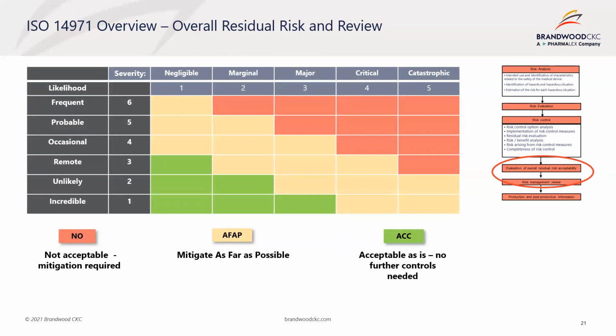ISO 14971 allows the manufacturer to perform a benefit risk analysis for those risks that are not judged acceptable using the criteria established in the risk management plan and for which further risk control is not practicable. The benefit risk analysis is used to determine if the residual risk is outweighed by the expected benefits of the intended use of the medical device. Benefit risk analysis cannot be used to weigh residual risks against business advantages or economic advantages, such as for business decision-making. This is crucial.